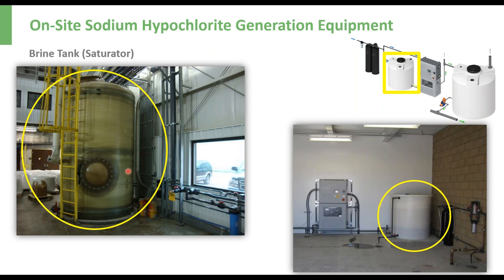We'll have the liquid level at about the 5 to 6 foot level, because we don't need to fill up the whole tank. The whole tank will be filled with salt, but on both the small open lid tank and even the brine silos, we have what we call a wetting ring, and it goes the whole diameter of the tank. When we need to add more water to the tank, it will wet in a circular diameter to help erode the salt evenly down as well.